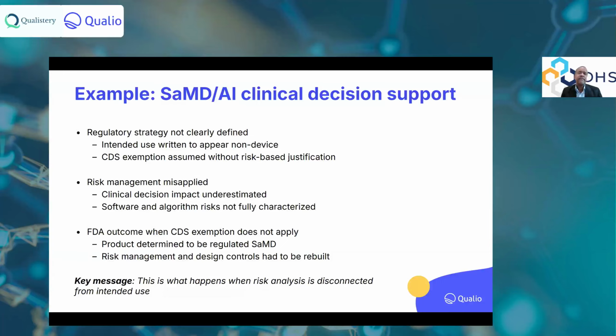low risk. If it does something, somehow connects to a machine and changes the dosage for the patient, it is not a CDS tool. It's a very important distinction. The AI could do something lighter, advise a physician who then writes a prescription, listening to the AI, or the AI changes the therapy. Very different. But your regulatory strategy will define which of these two it is.